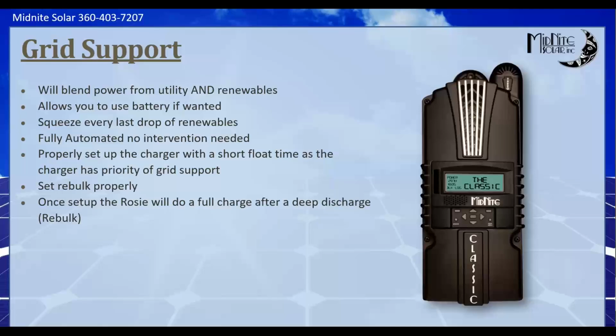So that's something to keep in mind: in grid support mode only, the charger takes priority over support mode. You do need to set up rebulk properly, because what you want in a perfect world with grid support is to have the system maintain itself from the renewables and ignore the grid. In my case, I dropped to 50% state of charge in the evening, and then I roll loads back over to the grid, but I do not charge the battery.